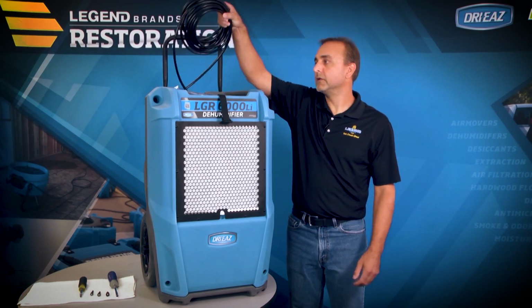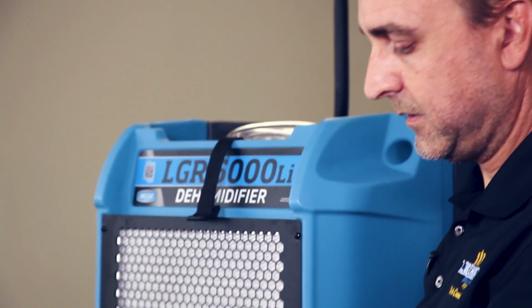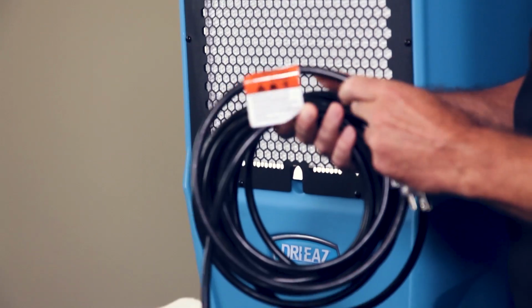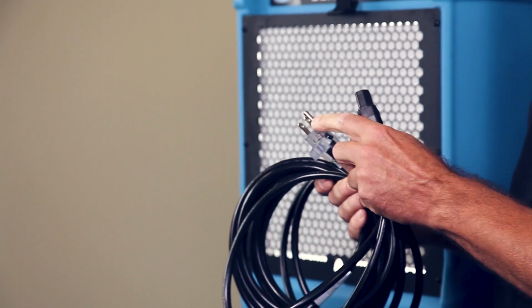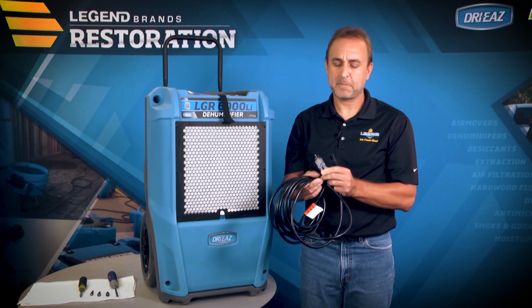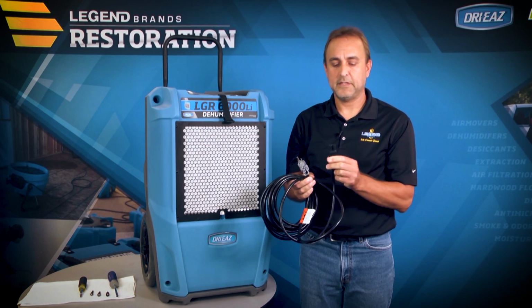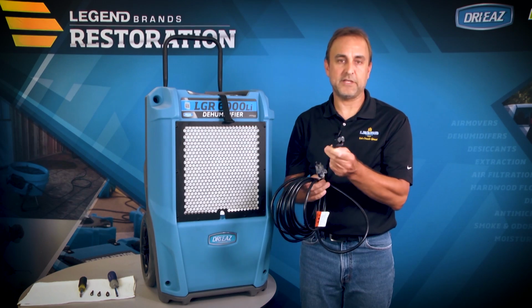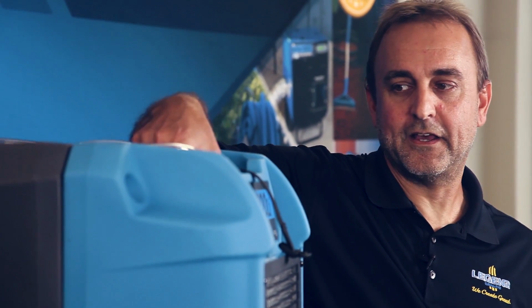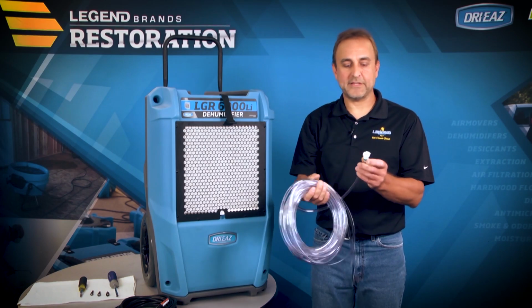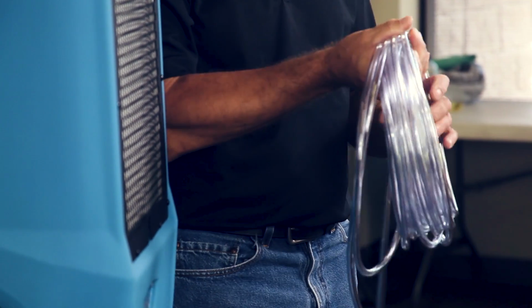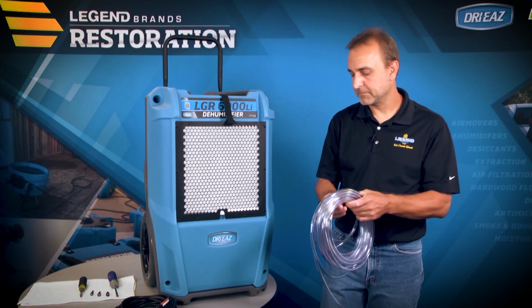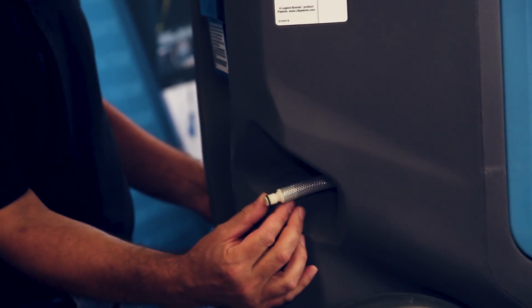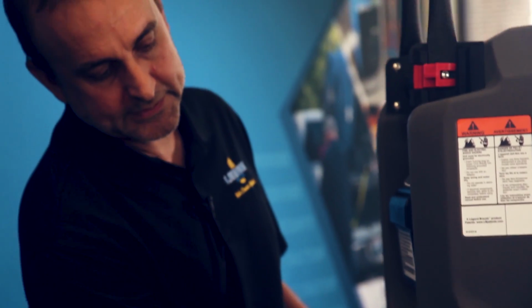Starting with the power cord, you want to inspect all throughout the entire run. Look for abrasions, cuts. Make sure the pins on the end of the plug are connected and not bent, and there's no damage or fraying to the IEC plug. Also inspect the condensate line. Check the quick disconnect that attaches to the unit, make sure it's not cracked. Check the length of the line to make sure there's no punctures. And on the back of the unit where the condensate line connects, inspect the quick disconnect there, make sure the O-ring is attached and there's no damage or chips to the disconnect there.